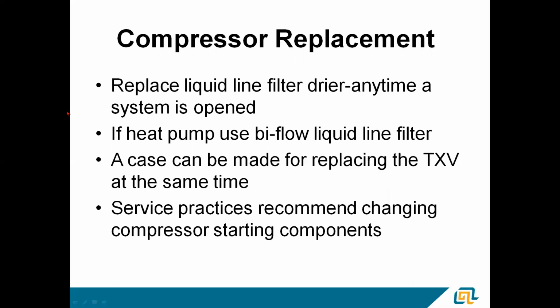If you're replacing a compressor, liquid line filter dryer, anytime a system is opened, and I don't even think that one's up for discussion, especially on R410A. You're cutting that thing out, you're opening that system up, please put in a new filter dryer. It'll save you a lot of hassle further down the line. If you're working on a heat pump, the liquid line filter dryer must be a biflow dryer. It's got to be able to flow that liquid in two directions.